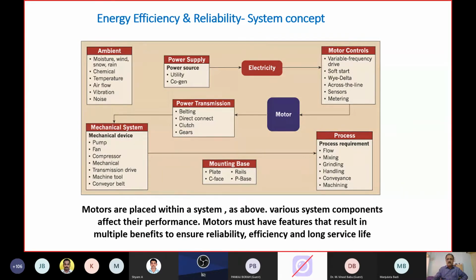I have explained this, so I leave this slide for your view later, to impress on you the fact that motors are surrounded by all these system components, and in some way or other they impact the performance of the motor. Performance, in terms of reliability or energy efficiency, is impacted by all these surrounding systems. So the motor has to be taken good care of if it has to live long. Almost 99% of motor failures are inflicted on the motor from external sources. This has to be understood.